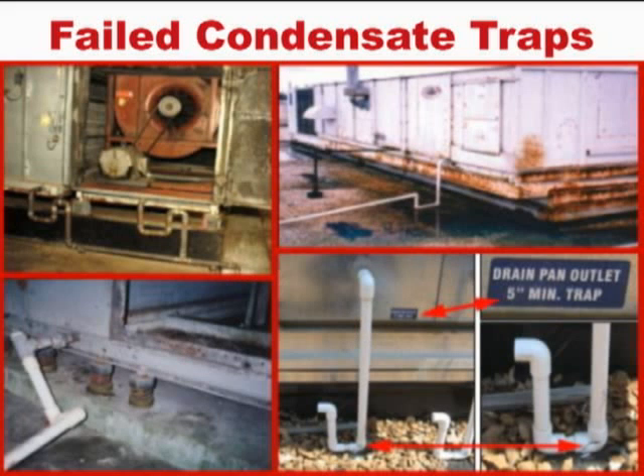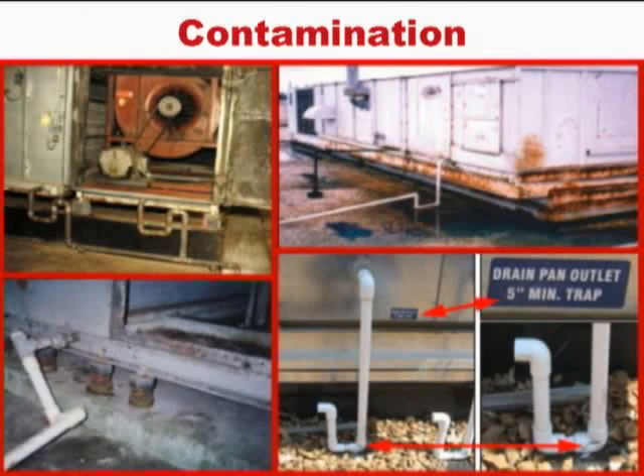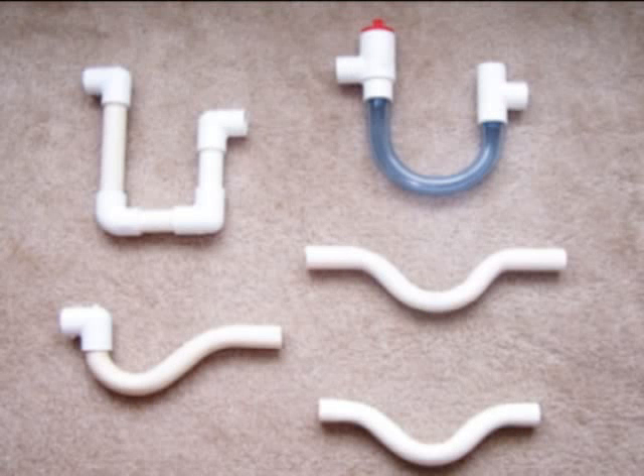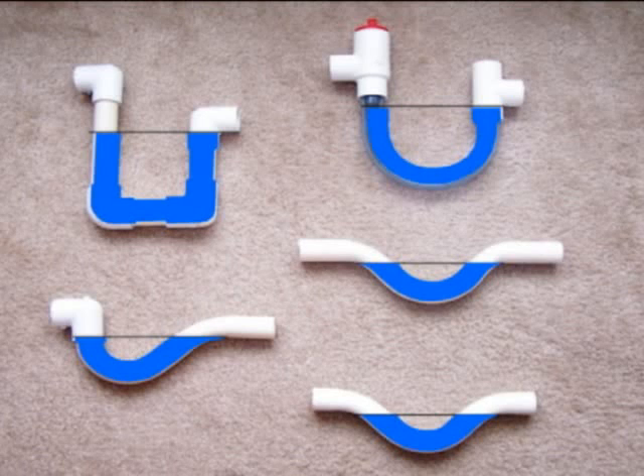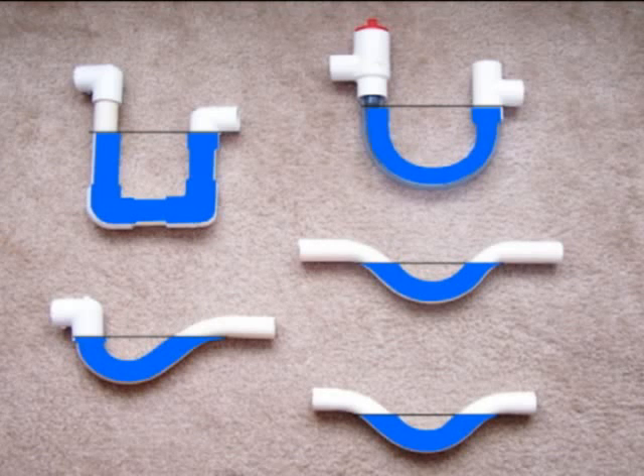For decades, air conditioners equipped with P-traps like those depicted here have been causing building owners excessive operating costs and indoor air contamination. The most commonly used condensate drain systems include P-traps like these. They use trapped water to form a drain seal and allow for condensate drainage. Although simple in concept, P-traps exhibit many failure modes that prevent reliable condensate drainage and expose surrounding areas to water damage.